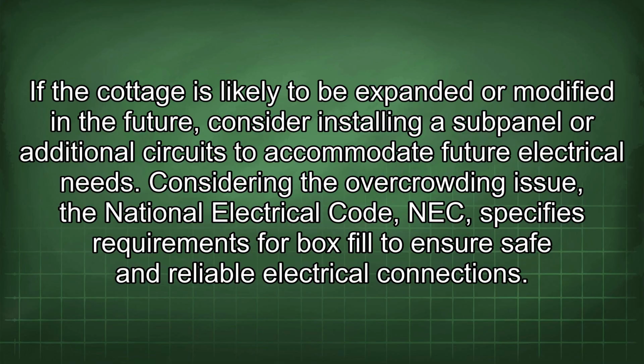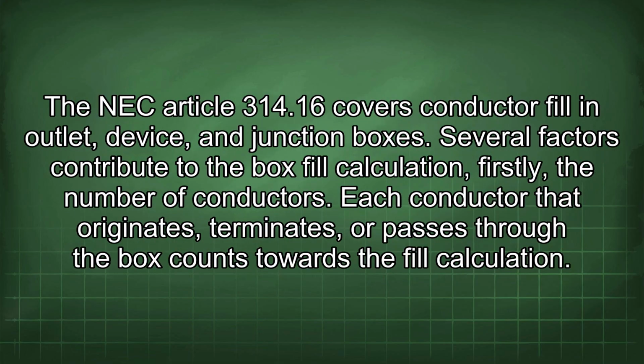Considering the overcrowding issue, the National Electrical Code (NEC) specifies requirements for box fill to ensure safe and reliable electrical connections. NEC Article 314.16 covers conductor fill in outlet, device, and junction boxes. Several factors contribute to the box fill calculation. Firstly, the number of conductors. Each conductor that originates, terminates, or passes through the box counts towards the fill calculation.